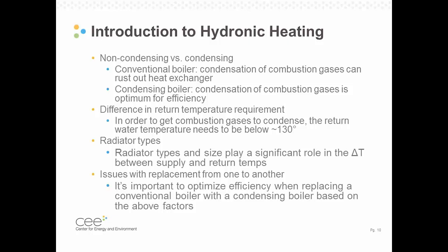One thing to note is that many condensing boilers are used as replacements for non-condensing boilers, so it's really important to think about these characteristics when putting in a different system than the originally designed system for that home. And so our project mainly looked at whether there are any issues with that replacement due to the existing configuration and the emitter type.